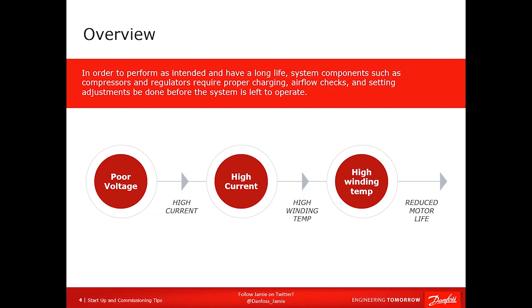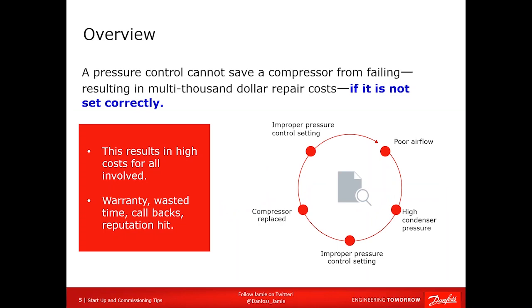However, if you have poor voltage resulting in high current, that raises your winding temperatures. The life expectancy of the winding insulation on a motor is directly related to the temperature of the winding. As the winding temperature increases, the life expectancy of the insulation decreases. It's a direct relationship, and that goes for any winding. You may not be operating this compressor to the point where you're breaking down the oil, but if it's operating hotter than normal, it will have a substantially shorter life expectancy.